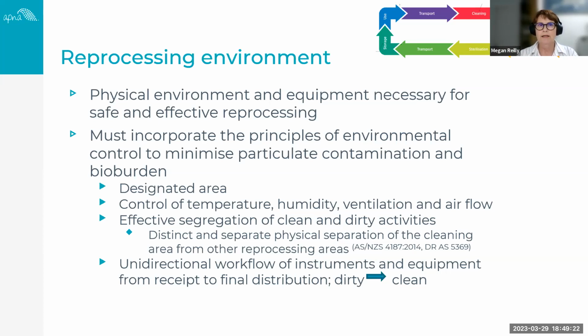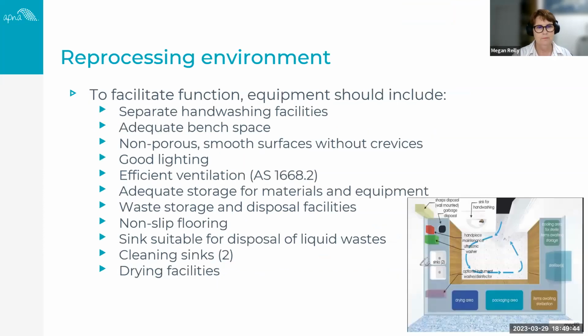We require currently a unidirectional workflow of instruments and equipment from receipt of the instruments into the reprocessing area to final distribution. So that may in fact be going back into your treatment room and into the designated sterile storage cupboards, drawers, or containers. So we're working from dirty to clean. In order to facilitate the function of the environment, the standard actually sets out the equipment that is required.